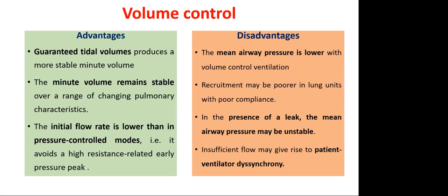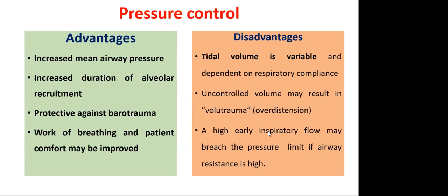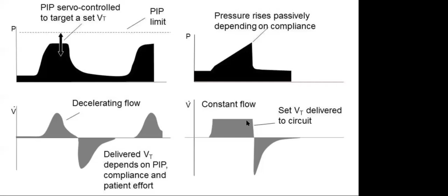So what is the advantage of pressure control? It will increase the mean airway pressure. It increases the duration of your alveolar recruitment, and the work of breathing and patient comfort may be improved. But it has disadvantages, like volume is not constant, it is variable. They can have volutrauma also. So you can see here some of the scalars. This is the pressure control and this is the volume control. You can see here pressure is constant after a certain time, whereas it rises slowly, and there will be decelerating flow in the flow scalar in pressure control, whereas in volume control it's a constant flow. But in recent ventilators, we have an option to change it to decelerating flow.